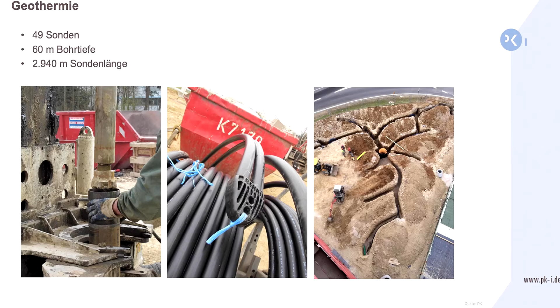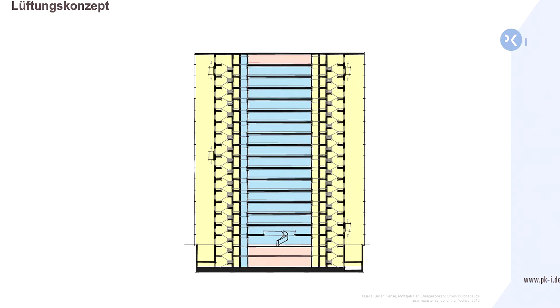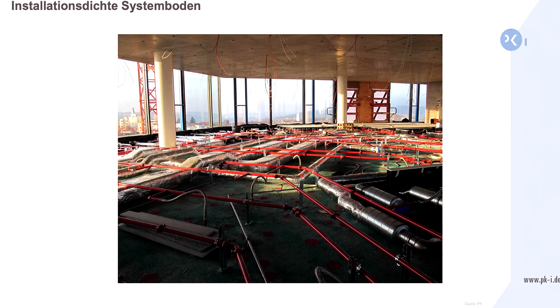The ventilation concept: we considered hygienic minimum air changes. So there's no air conditioning through the air in the building, which would be the classical approach, but costs a lot of energy. Air is only transported such that it corresponds to the hygienic personal air exchange, and on top of that, it's also controlled by means of CO2. That's what it looks like. The concrete ceiling is equipped with these pipe hoses. The concrete core activation is there, and the visible concrete ceiling, which stays free, accommodates the sprinkler devices. So there's a very high density of such technical facilities.